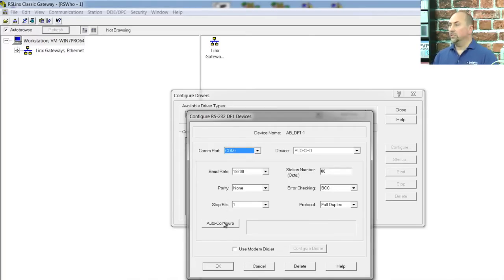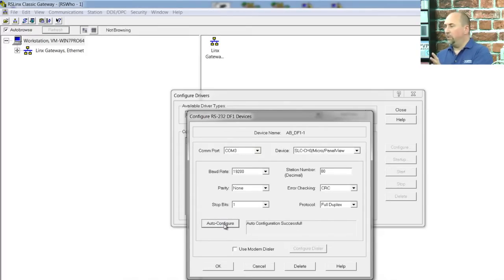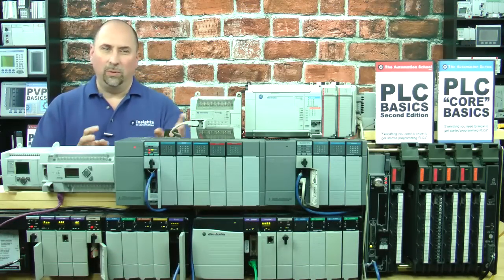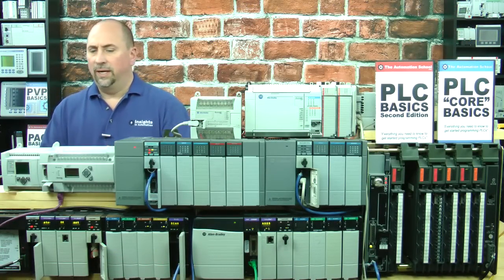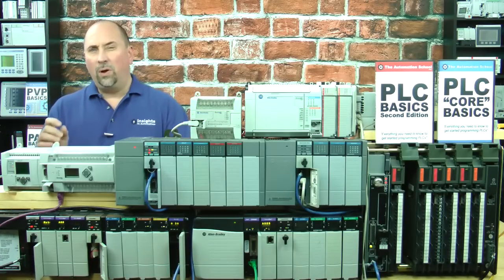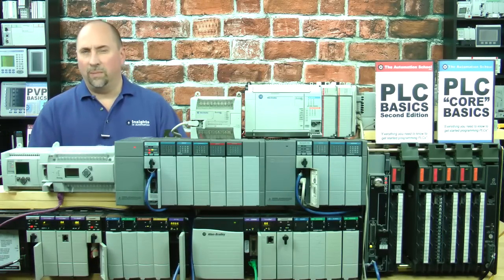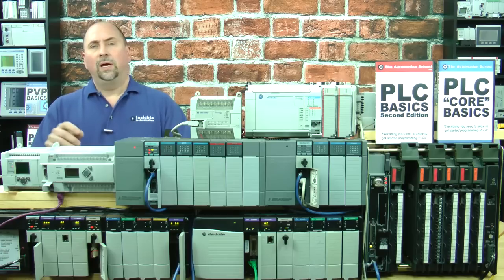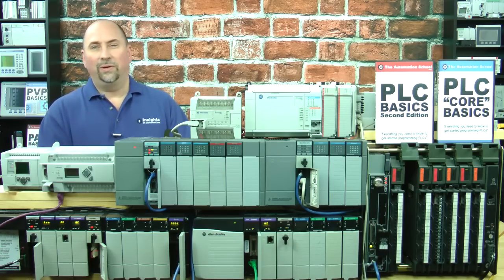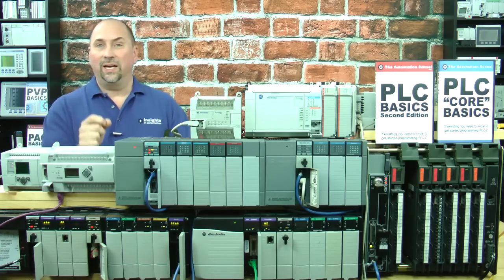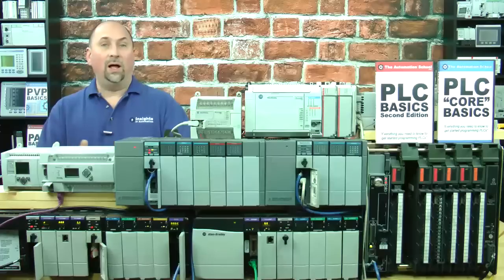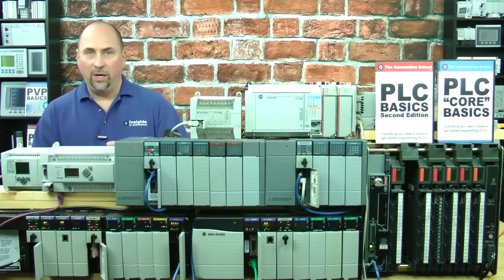The Auto Configure button has been there for years and years. When I click it, you can see it very quickly went through and found all the settings. Now if that doesn't work for you, there are a couple of things that can cause that — it could be a bad cable or a bad port on the unit, which is rare. But more than likely the port is set up to talk some other protocol, like Data Highway 485 or DF1 half duplex. The nice thing about the 1100 that the 1000 doesn't have is it has a DCOM button right on the unit that you can press to toggle back to default communication settings. Very cool.